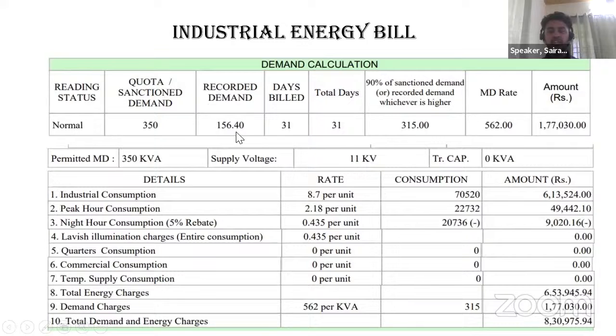During the operation of the industry, the demand was recorded by the trivector meter installed by the grid. The recorded demand is 156.40 kVA. This is far less than the contract demand that they have agreed with the grid. But there is a clause on the billing demand: 90% of the sanctioned demand or the recorded demand, whichever is higher, has to be paid. The recorded demand is not even close to 90% of the sanctioned demand. It is 156, less than 50%. So as per this clause, you have to pay for 90% of the sanctioned demand. 90% of the sanctioned demand of 350 will be 315.